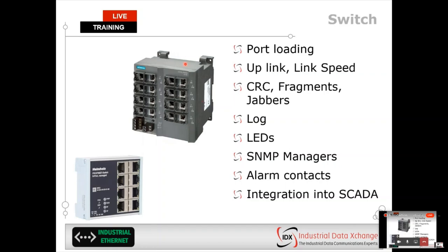These switches would have an integrated log telling you if a device was lost at any point, so immediately you have your remote monitoring solution there: LEDs such as uplink and link speed communicating status, but also a bus fault LED telling you there are errors in the network. If you have bus fault lights on your network components, please don't make it the new norm — rather clear whatever's creating that bus fault light.